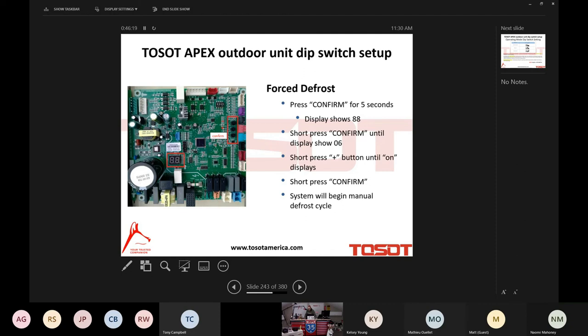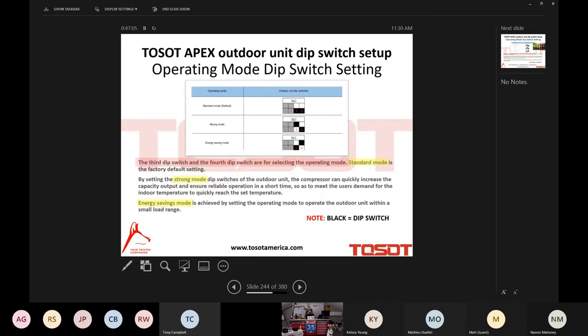Beautiful thing. Your service tech can force defrost. Again, all done at the outdoor unit. Something I got to be careful with, open bottles of water with all the electronics here. But I do want to show you this. On the outdoor board, where are the dip switches again? There we are. The dip switches are here. But you also have the series of 3 buttons, actually 4 buttons right here. By manipulating these buttons, there is a variety of things that your service tech can initiate, and one of them is forced defrost. So that's a beautiful thing for our service techs out in the field to know and be able to enable that.